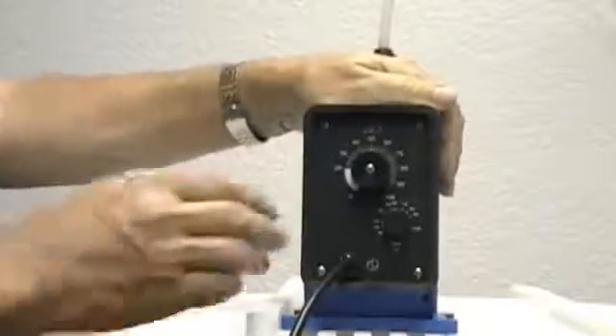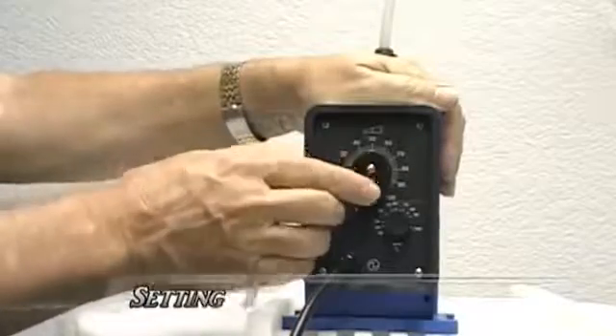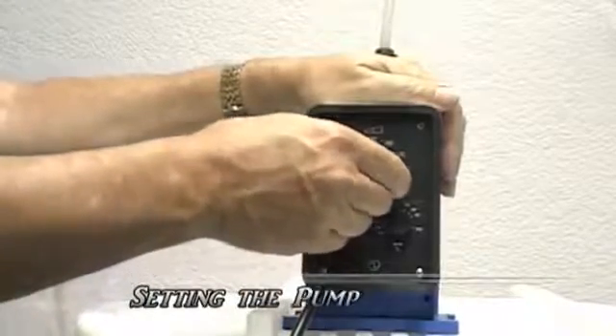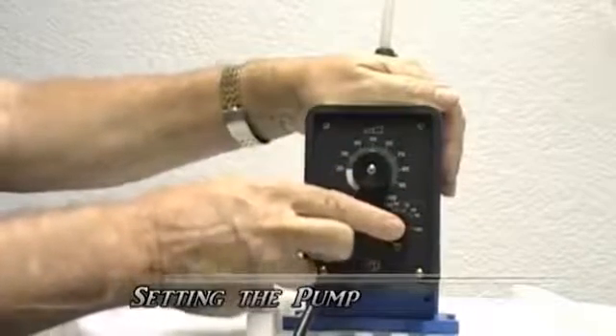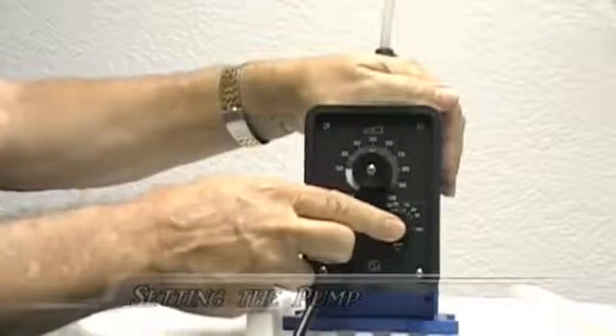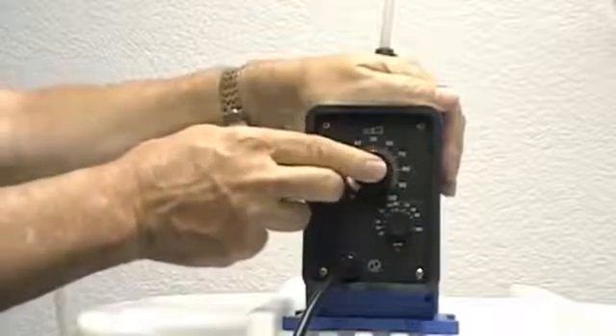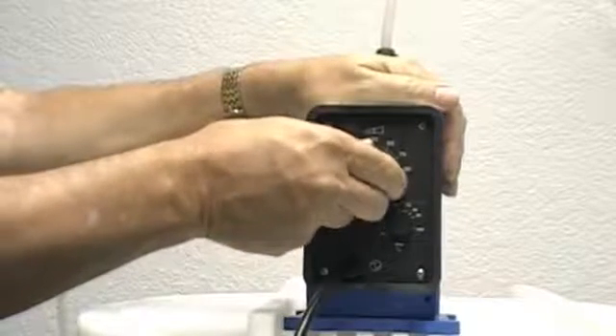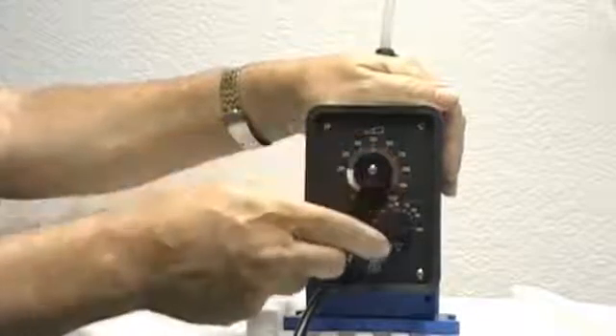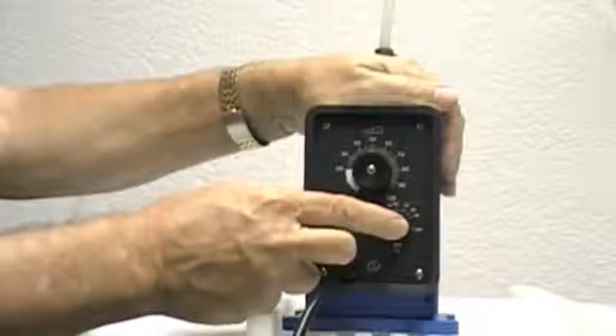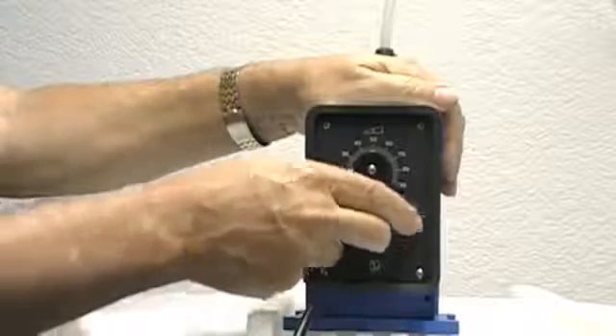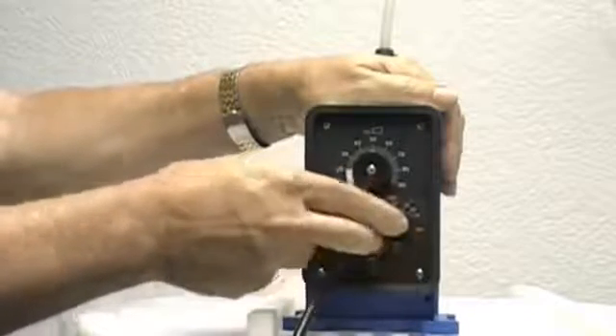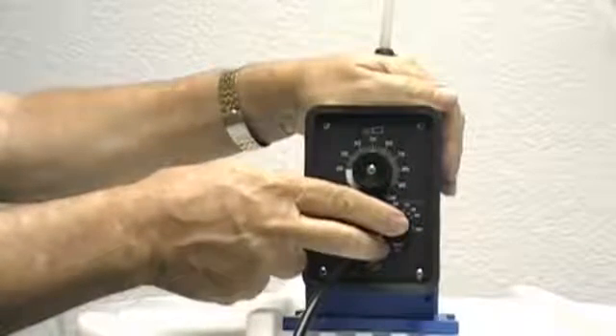The Pulsatron A Plus pump has two adjustments. This adjustment is the stroke length adjustment and this adjustment is the pulse rate adjustment. The stroke length adjustment adjusts the amount of flow per stroke. The stroke rate adjustment adjusts the number of strokes per minute. At 100% there would be 125 strokes per minute.